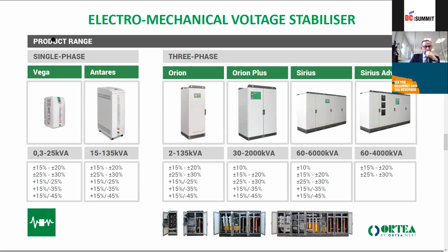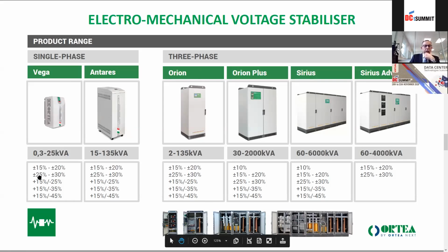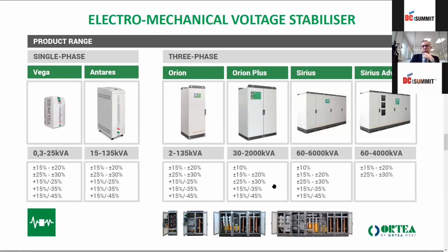You can see here that we have different types of models that can be single or three-phase. In single phase, we can reach 135 kVA, and in three-phase, we can reach 6,000 kVA. You can see here that we have different solutions with different configurations, etc. Also, the range of variation can be symmetrical or asymmetrical. That can also be driven to all the units, so all the units can have the same range.